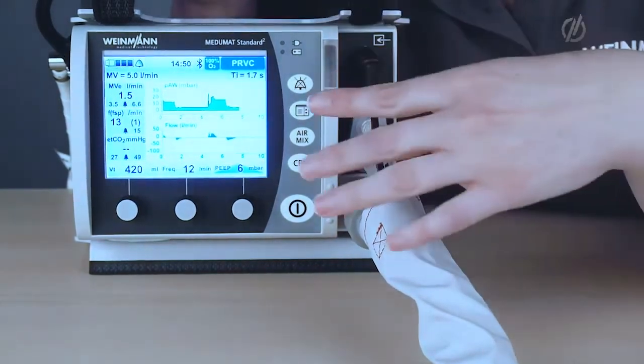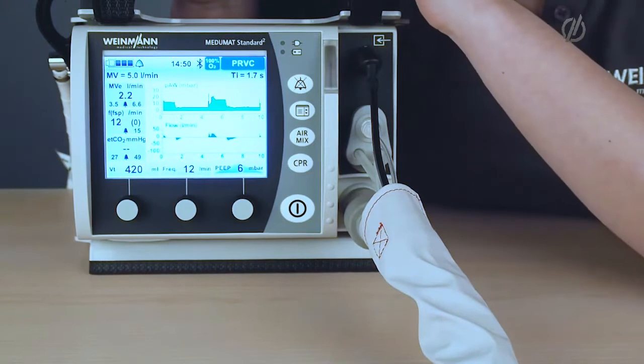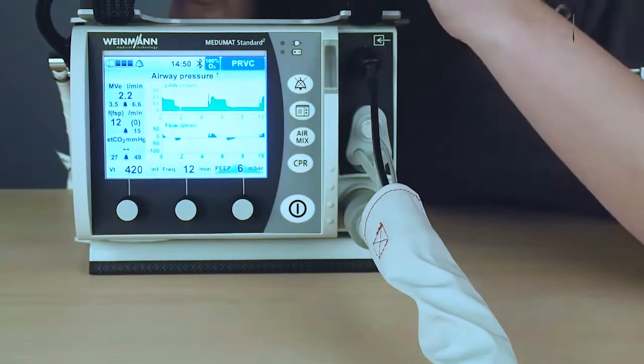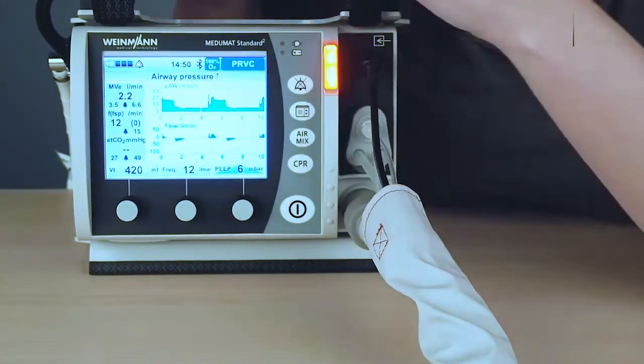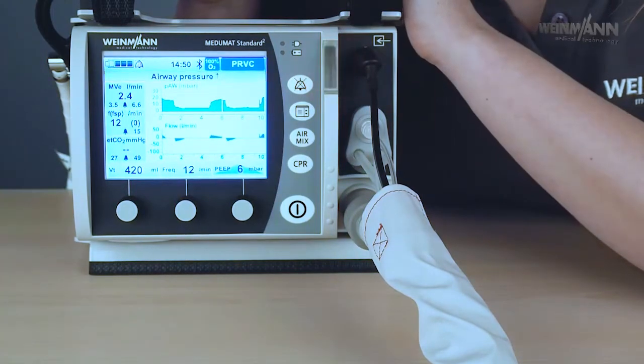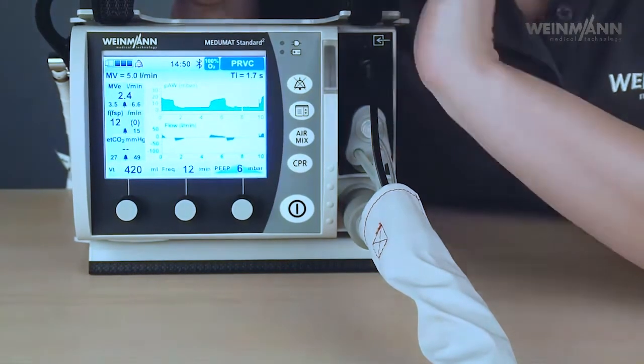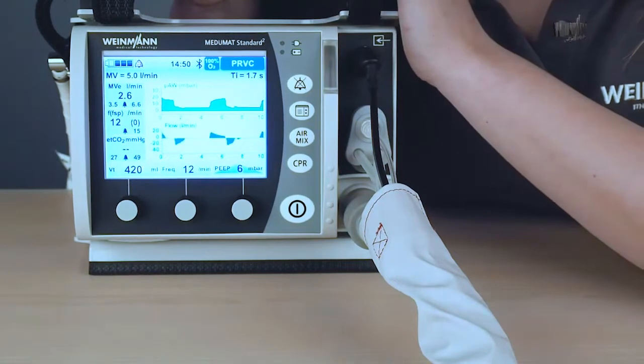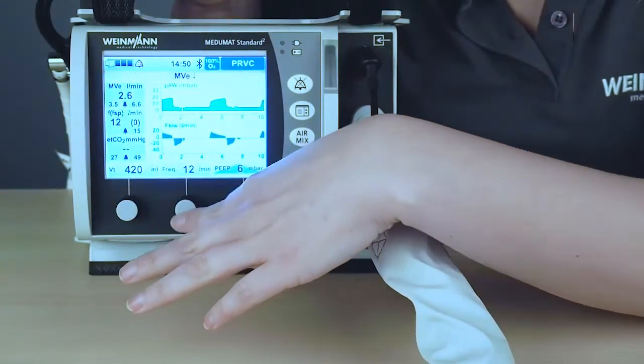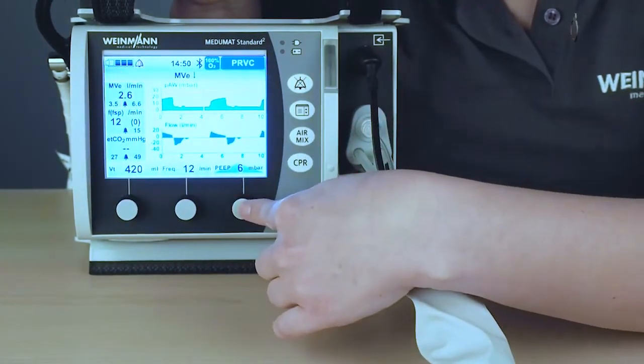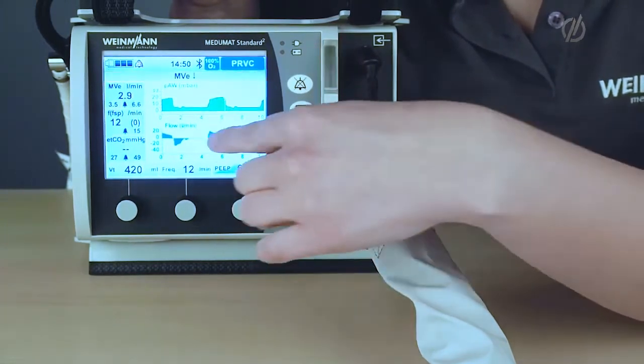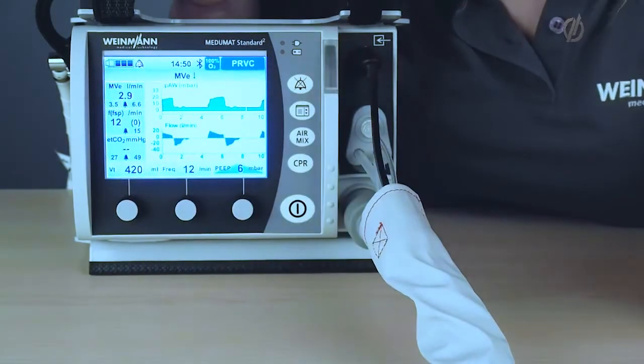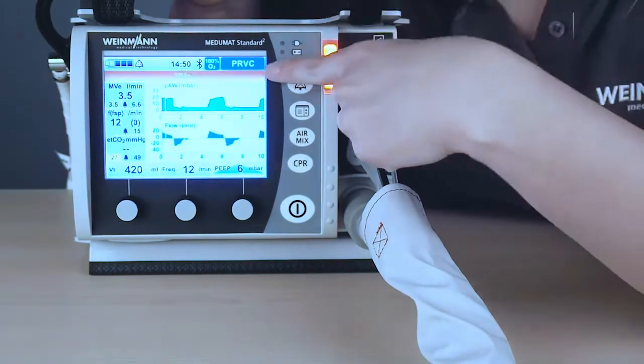Now quickly show you how the screen works. So we here have the ventilation curves. So the pressure curve and the flow curve. We have here the settings, the ventilation settings that you can do. We have here the measurement values on the right hand side, and here you have the status line.